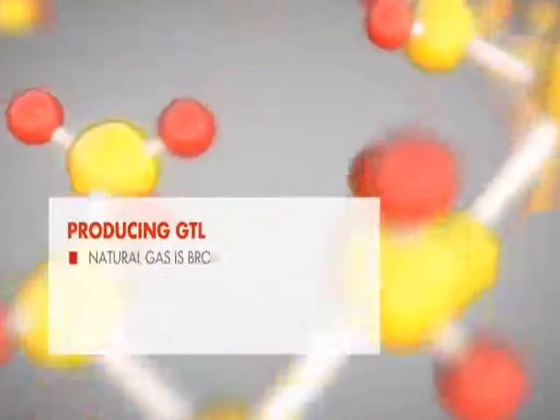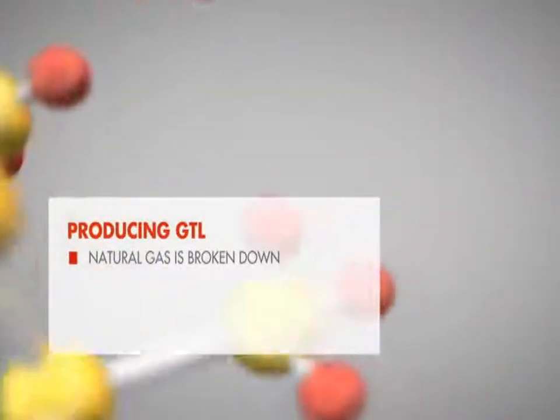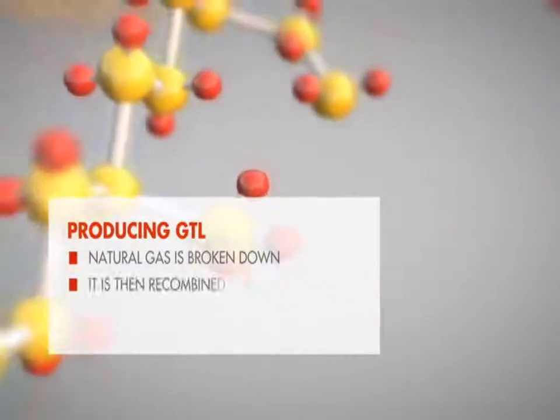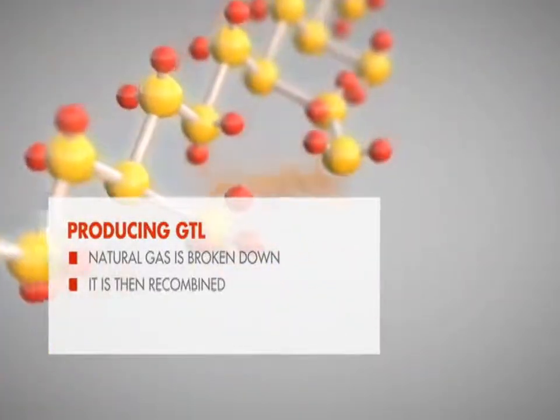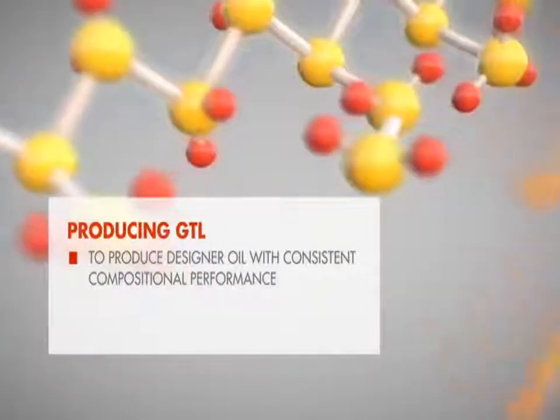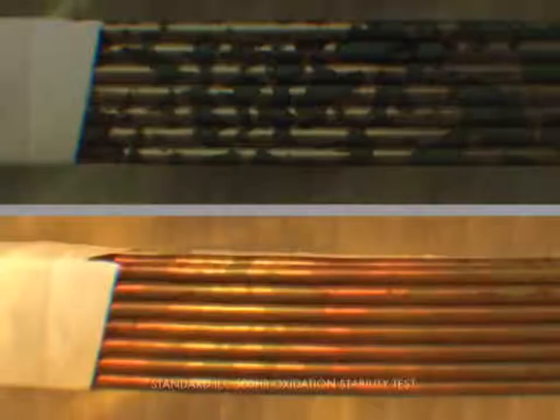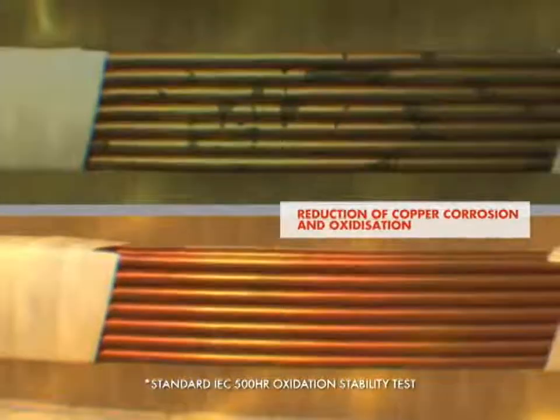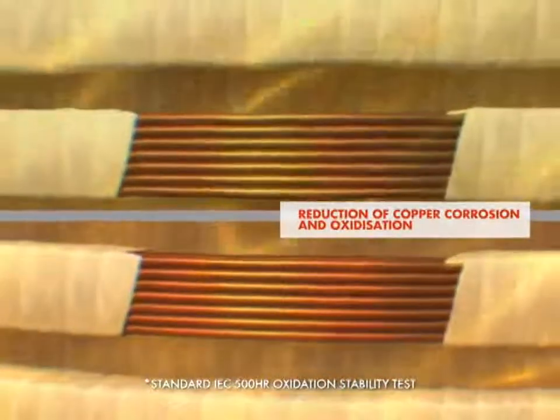One of the benefits of the new Diala S4 ZX-I is the fact that it's based on gas-to-liquids technology. This is based on taking natural gas and breaking it down to its constituent parts, then recombining that to make a manufactured, bespoke, designer transformer oil. We now have an oil which has no sulfur, which removes the potential for copper corrosion and failure of a transformer. In addition, the lifetime performance is up to 5 times better than the standard grade.